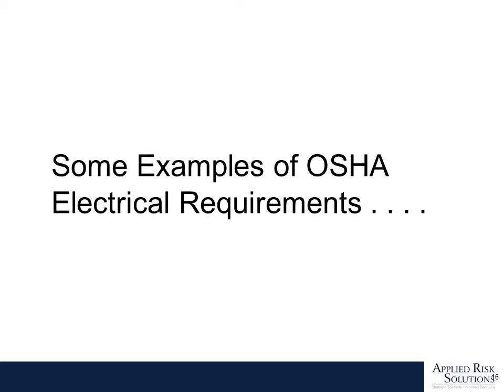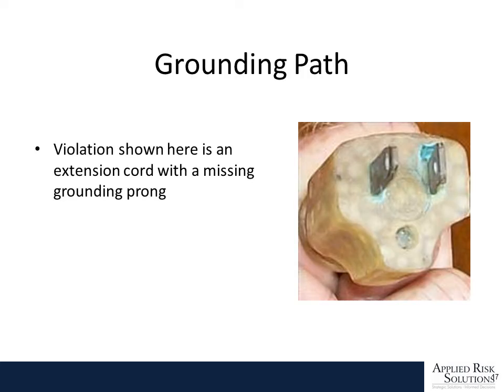Here are some examples of OSHA violations. Here's a ground plug where somebody needed to plug this in. They didn't have a 3-prong outlet, and so they cut off the ground. This is unacceptable. If you have an appliance that has a 3-prong cord, you must plug it into a 3-prong outlet. Older homes only have 2-prong outlets if they've not been rewired up to code. There are a lot of extension cords made for lower voltage things like Christmas tree lights that only have 2-prong outlets. You may not use a 3-prong plug in an extension cord designed for 2 prongs. This is a serious OSHA violation and a serious hazard.